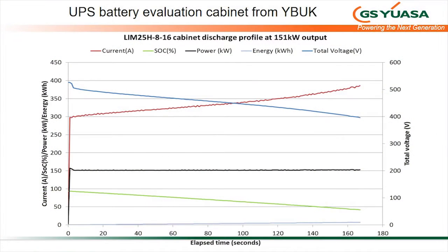That doesn't occur with lithium ion, which is very useful at high rates, because with lead acid that initial voltage dip can sometimes cause things to trip out in fractions of a second, which is a big problem at very high power. Lithium ion doesn't have that characteristic. So it's a nice gentle drop off, nothing exciting. Take that up to 150 kilowatts in the cabinet, and now you're getting just under 3 minutes of discharge, but still looking pretty much the same, tapering off in voltage. Current increases to maintain constant power. So it behaves in a very predictable and easily understandable fashion.